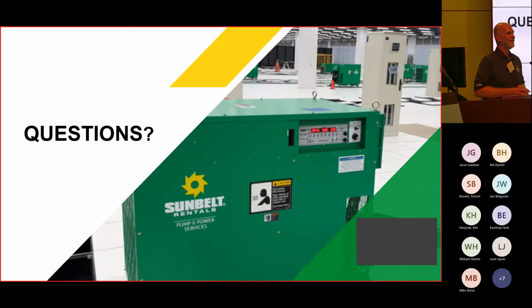Second question: can you handle unusual voltages? I'm seeing a lot of clients moving to 415 volt systems. Can you handle 415? Yeah, we'll provide a 400 kW unit rated at 480 and it will derate. If you do the math, 415 squared divided by 480 squared gives you the derate factor, which you apply to 400. I don't remember the exact math, but yes, it won't be a full 400 kW load since we have to derate.